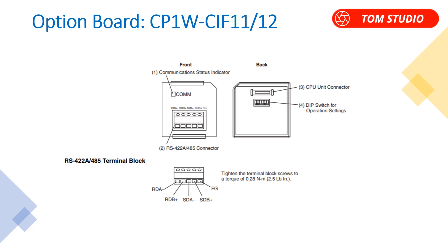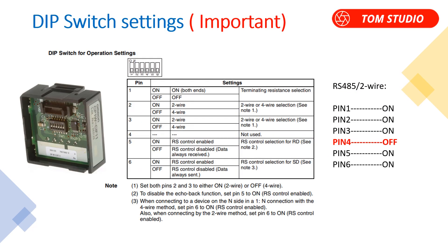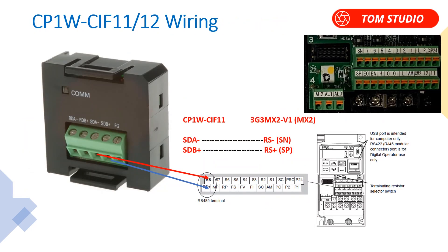The wiring diagram is quite straightforward — just use two-wire RS485 to link the master device and slave devices together. Heads up: it is necessary to set up the CP1W CIF11 DIP switches, otherwise communications will not proceed and you will keep getting 0080 and 8088 error codes in the function blocks. In this example, we set all DIP switches on except PIN 4, which is off. You can use either RDA/RDB or SDA/SDB — I chose SDA and SDB because the frame grounding FG terminal is right next to them, making wiring a bit easier.